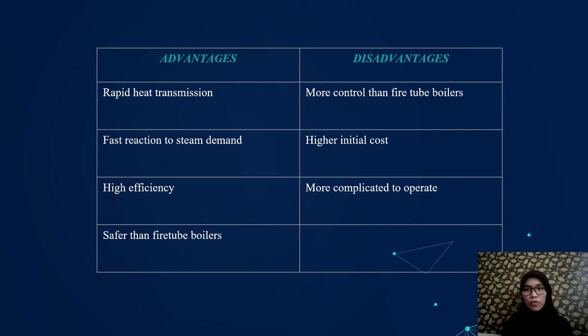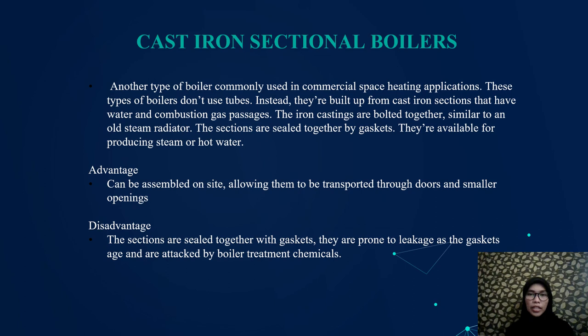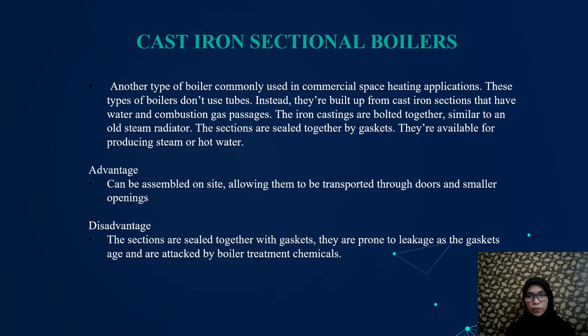Other than fire tube and water tube boilers, there is also the cast iron sectional boiler, another type commonly used in commercial space heating applications. This type of boiler does not use tubes and is available for producing steam or hot water. An advantage is that it can be assembled on site, allowing it to be transported through doors and smaller openings. A disadvantage is that the sections are sealed together with gaskets, which are prone to leaking when attacked by boiler treatment chemicals.